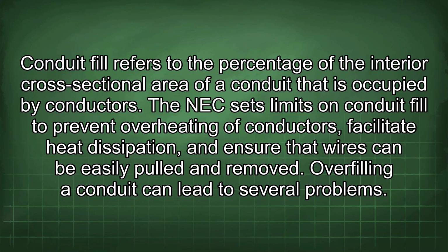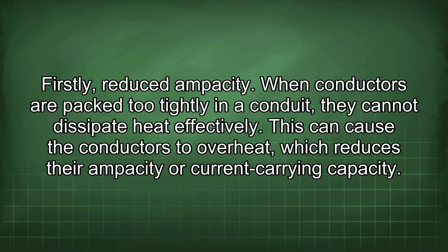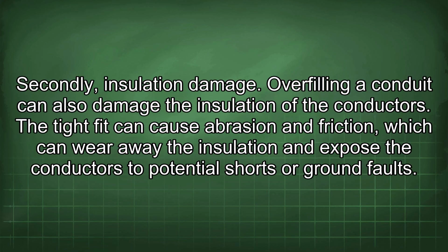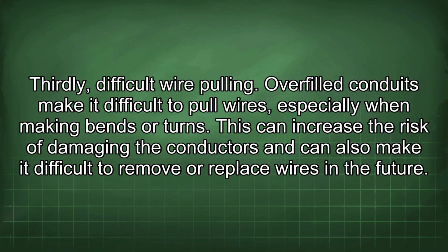Overfilling a conduit can lead to several problems. Firstly, reduced ampacity. When conductors are packed too tightly in a conduit, they cannot dissipate heat effectively. This can cause the conductors to overheat, which reduces their ampacity, or current carrying capacity. Secondly, insulation damage. Overfilling a conduit can also damage the insulation of the conductors. The tight fit can cause abrasion and friction, which can wear away the insulation and expose the conductors to potential shorts or ground faults. Thirdly, difficult wire pulling.